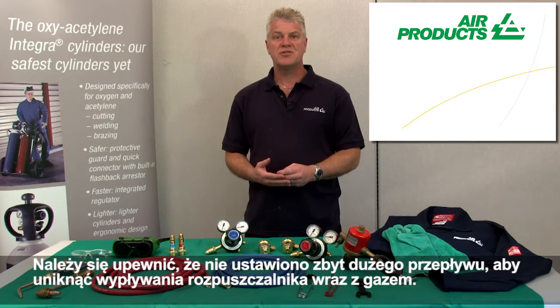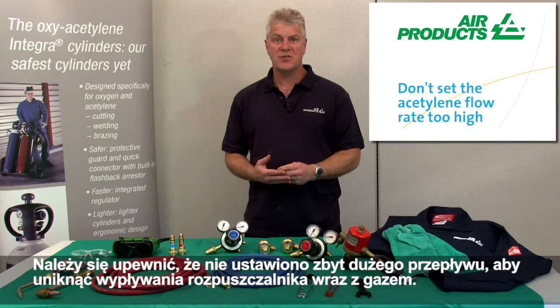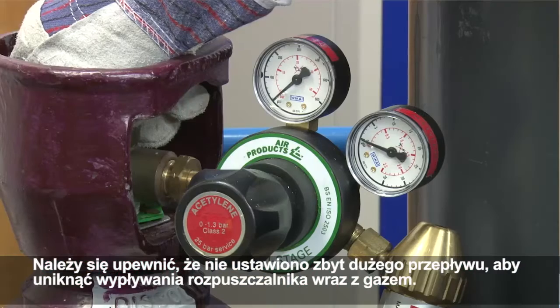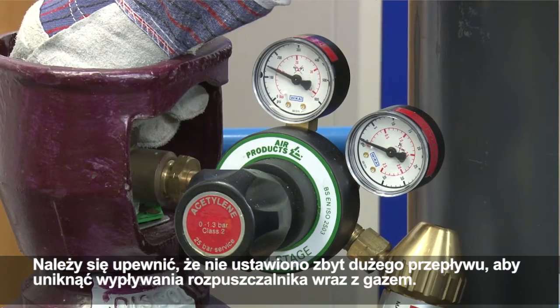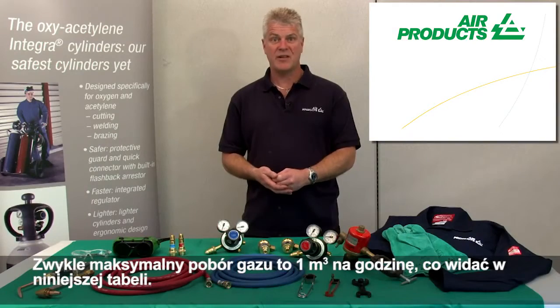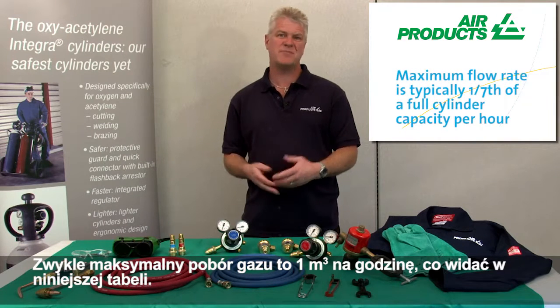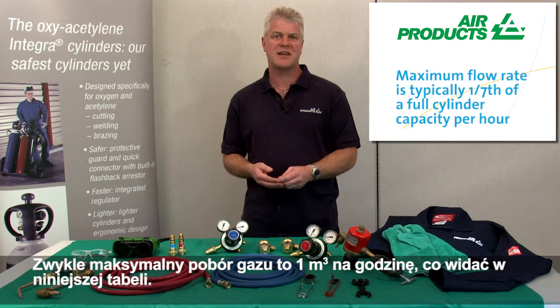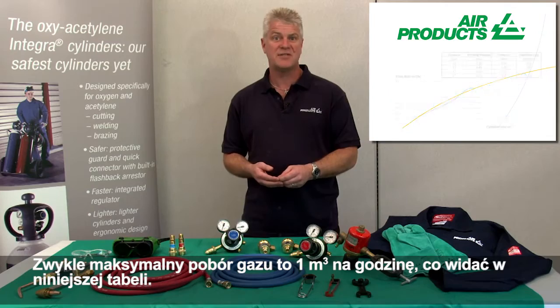It's important to ensure that you don't set the flows too high on acetylene tools to avoid pulling the solvent out with the gas. Typically, the maximum withdrawal rate is taken to be 1/7 of a full cylinder capacity per hour, as you can see in this table.